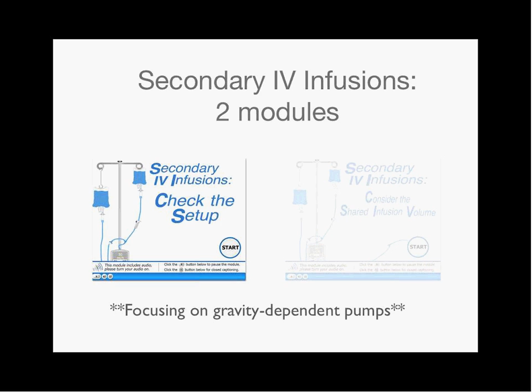So I'll show a few short clips from the Check the Setup module, so you can get a feel for how these modules have been designed. The first shows an example of the engagement question I discussed at the start of the module. In this case, a nurse hung a 1-liter normal saline bolus as the secondary infusion. At 2 hours, when the secondary infusion is supposed to be complete, the nurse comes back to find significant volume left in the secondary bag, so she reprograms the secondary infusion to measure the residual, which is about 100 milliliters, at the secondary rate of 500 milliliters per hour. And the question is then asked of the viewer: do you hit start? I'll just play the clip now.